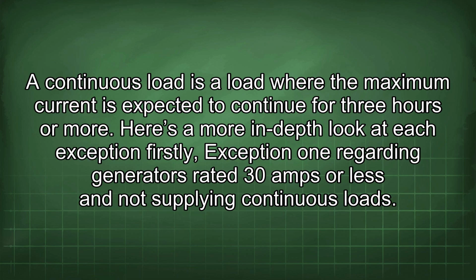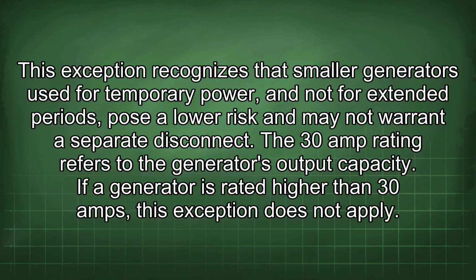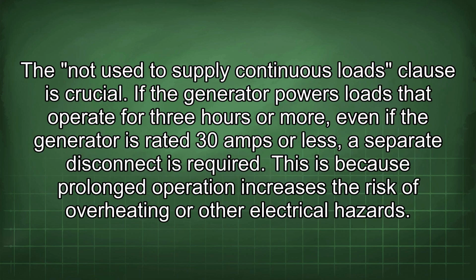Firstly, exception 1 regarding generators rated 30 amps or less and not supplying continuous loads. This exception recognizes that smaller generators used for temporary power and not for extended periods pose a low risk and may not warrant a separate disconnect. The 30 amp rating refers to the generator's output capacity. If a generator is rated higher than 30 amps, this exception does not apply. The not used to supply continuous loads clause is crucial. If the generator powers loads that operate for 3 hours or more, even if the generator is rated 30 amps or less, a separate disconnect is required. This is because prolonged operation increases the risk of overheating or other electrical hazards.